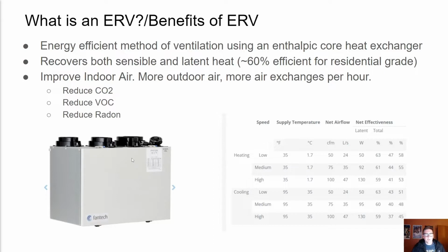Now, how an ERV works is all ERVs have 4 duct connections. One of the connections is return air, where it pulls air from inside your house. That air is run through a cross-flow enthalpic heat exchanger. And so that return air exchanges its heat with outdoor air that you bring in from the outside. In the summertime, it pre-cools your air as it comes in. In the wintertime, it preheats that air before you then transfer that fresh air, which is now supply air, into your house. And then that return air, once the heat is exchanged with the outdoor air, is then exhausted.